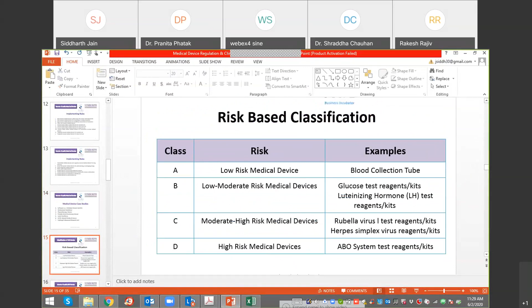Now I will be taking care of the risk-based classification for the in vitro diagnostic devices. For the in vitro diagnostic devices, they are again classified into class A, B, C, and D. For the low risk medical devices, like blood collection tubes, they are class A. All the low moderate risk medical devices, like the glucose testing kits and the luteinizing hormone testing reagents, are class B type of medical devices.